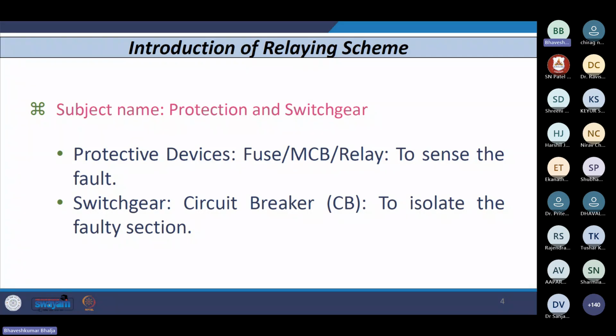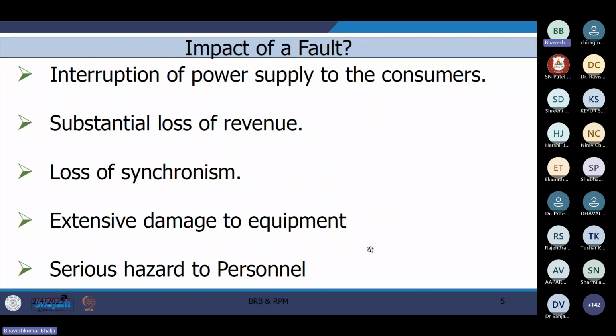Now, if you look at the conventional protective devices, whether we use fuse, MCB or relay, which is used for sensing the fault, that remains the same whether we use it for AC system or DC system. Along with that, the relay and MCB, if we set aside the fuse, are meant only for sensing of the fault. The isolation task is to be performed by some other device known as the circuit breaker. In the same way, in AC or DC system, we have a similar type of mechanism.